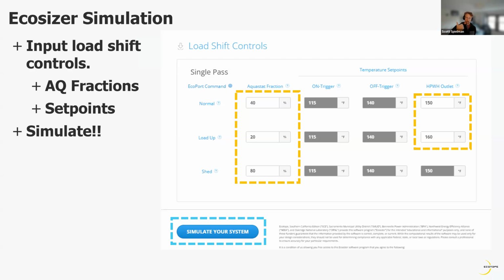So if our operating modes are normal, load up, and shed, in normal, we're going to be turning on at a temperature sensor that's 40% above the bottom of the storage tank, if we're just with one storage tank. In load up, we're going to turn on at a temperature sensor that's 20% up from the bottom of the storage tanks. So in the load up scenario, we are pushing heat from the top of the tank down further in the tank and storing more heat in that thermal energy storage system. And in load up, we can also adjust the heat pump water heater outlet temperature, so we can inject hotter water into the top of the storage tank to increase the density of our thermal storage as well.